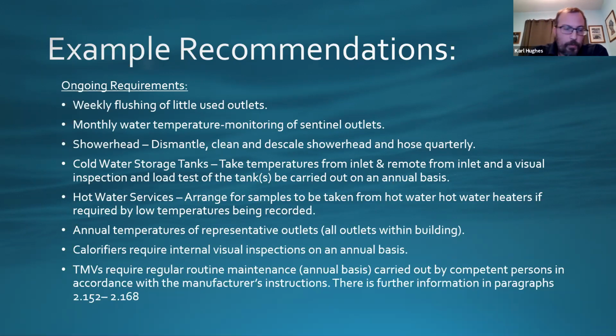Hot water, there's no requirement that says you have to take Legionella samples. The only time you would take Legionella samples is if any of the control measures we detailed above show that the system's at risk. For example, if the cold water is repeatedly above 20 degrees, or if the hot water is repeatedly below 50 degrees at the outlet, then you would take a Legionella sample to see what's going on in the system. You make sure that every outlet within the building, for example cleaners' sinks, kitchens, all the wash hand basins and things like that, has been tested for temperature at least once a year.